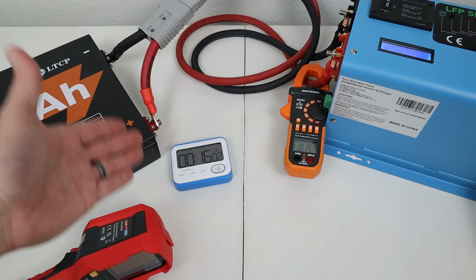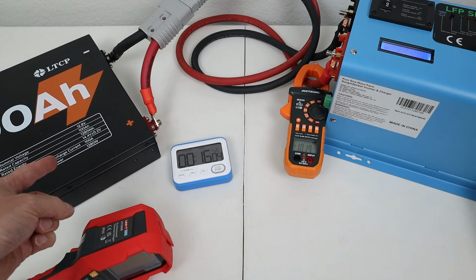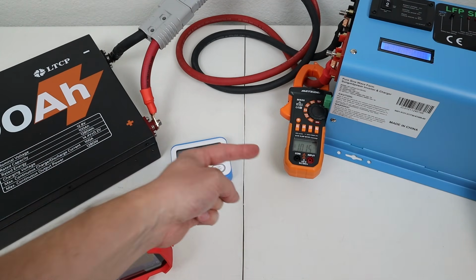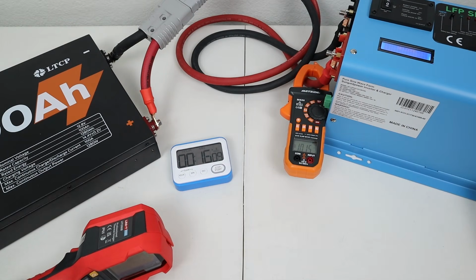So it's actually been 16 minutes of running the 100 amp load. You can see on my clamp meter here, it's showing 101.5 amps. Now I just want to check the temperature to make sure everything's good, so let's go ahead and check it out with my thermal camera.